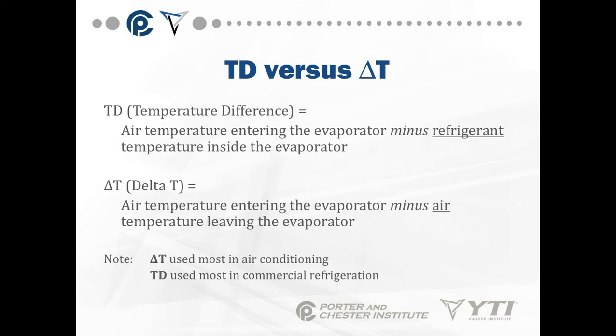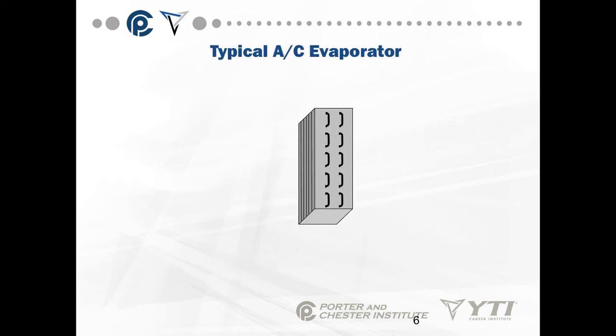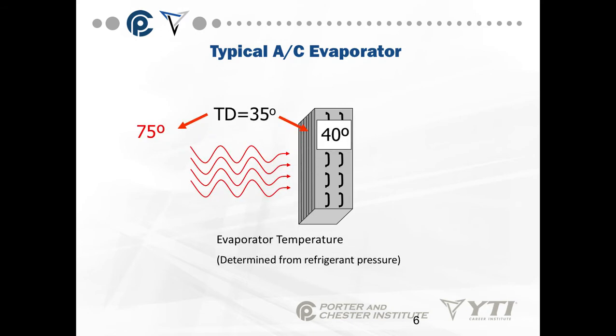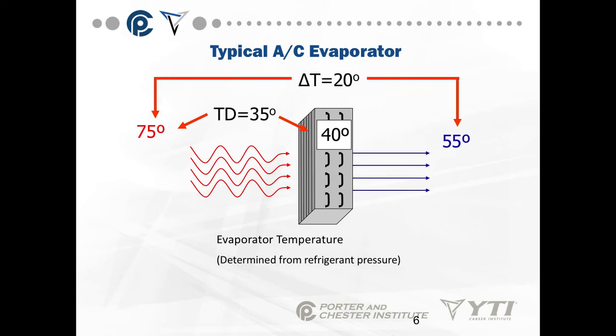Don't get the two confused, because technical support and technical documents will sometimes list both of these. Delta T is most often used in air conditioning; temperature difference is most used in commercial refrigeration. For a typical AC evaporator: air coming in at 75°F, refrigerant boiling point at 40°F, temperature difference is 35°F. The air leaving has been cooled from 75°F to 55°F, so delta T is 20°F.